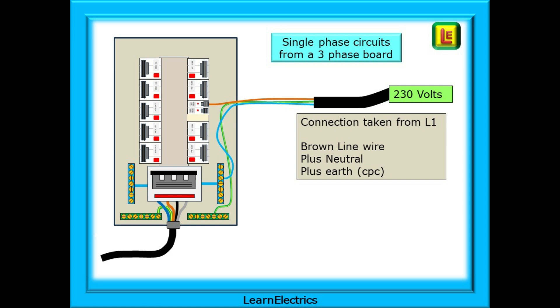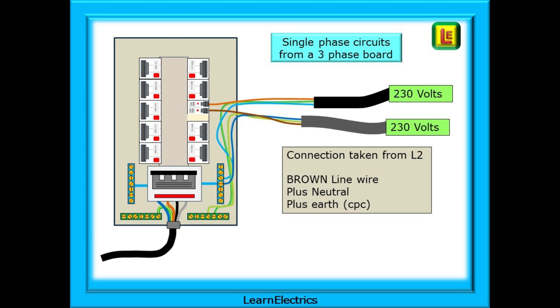Here we've taken the line from the L1 terminal. We can also take a single-phase supply from the L2 terminal. Simply install a single-phase circuit breaker into the appropriate position and make your connections as before: line, neutral and earth. We now have two cables with two brown wires, one in L1 and the other in L2. Be very aware that there is 400 volts difference between these two brown wires. We cannot, we must not, mix the wiring to these circuits. If we do, expect a bang!